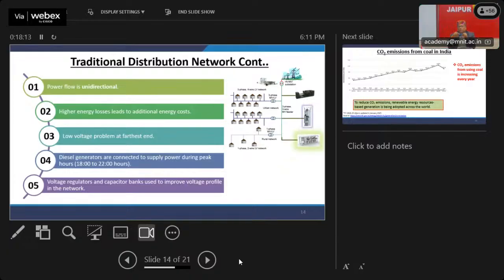So higher energy losses lead to additional energy cost, and the distribution system experiences the maximum energy loss, almost 3 to 5% in transmission and 18 to 20% in case of the distribution system. That is due to two things. One is the current is very high, because when the current is more, the I square R loss will be very high. And then there is the low voltage problem at the farthest end, as I told you. And diesel generators are connected to supply power during peak hours, which is not true in small towns, but in a city like Jaipur, whenever there is an energy peak, we don't experience power cuts. That is because there are some diesel generators which are operating during peak hours.